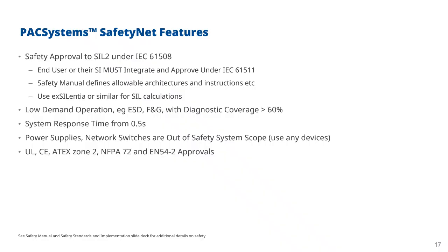So here's a summary of the PACSystems SafetyNet. It's safety approved to SIL 2 under IEC 61508. So again, note that's hardware approval. The end user or their integrator must integrate and approve under IEC 61511, which means performing that functional safety assessment and following the results of that assessment. The safety manual defines allowable architectures and instructions.